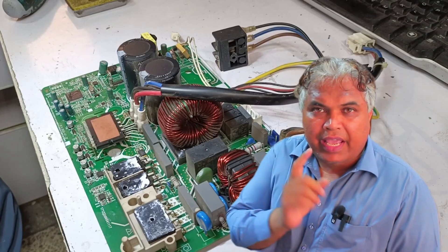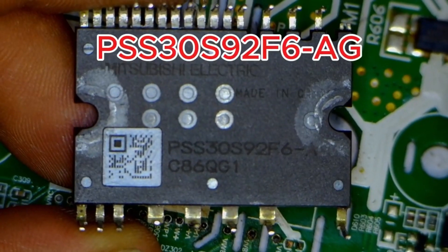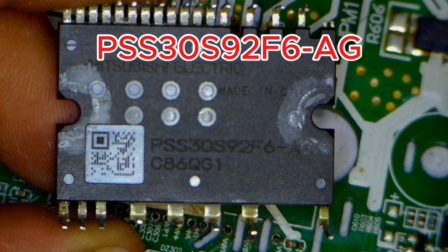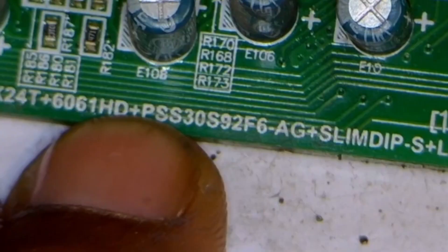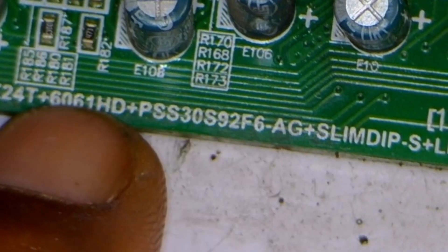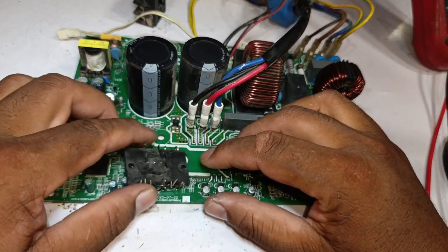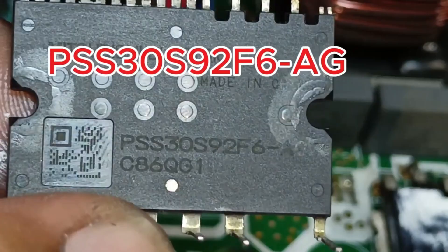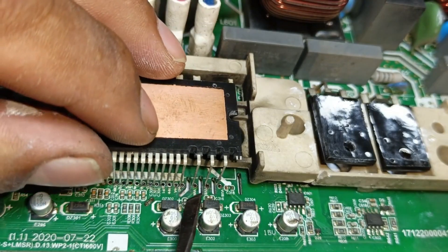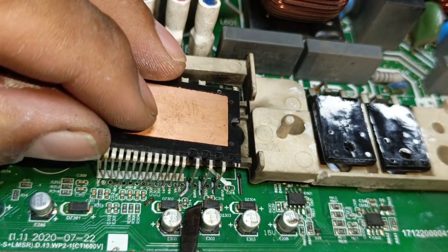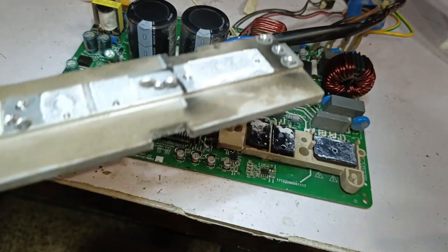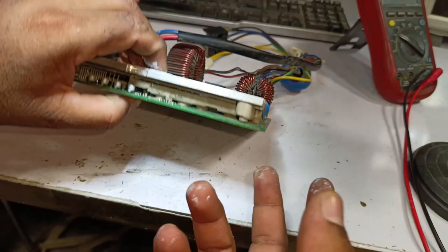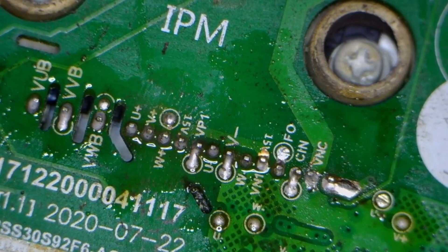Now we are installing the new IPM intelligent power module, and its original number is PSS30S92F6-AG. If you look closely, the PCB number is also written on it, showing its original number. The original IPM that was removed had its number erased, but the new one has the correct marking. We will install the IPM properly, ensuring that each pin is carefully placed. Now the IPM is in place, and we've attached its base plate on top. All screws are tightened, and the IPM is soldered.